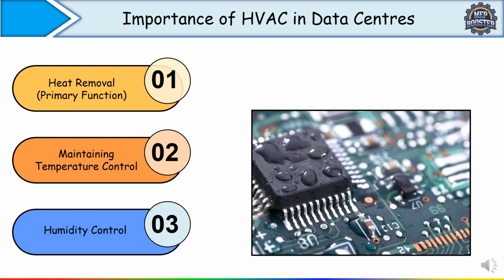Now the third one is humidity control. HVAC also regulates moisture level in the air, usually kept between 40% to 60% relative humidity. Why does it matter? Because too high humidity causes condensation, water droplets on circuits, and short circuit problems. And if humidity is too low, it increases static electricity and electrostatic discharge, which can damage sensitive components. So we need to control humidity too.